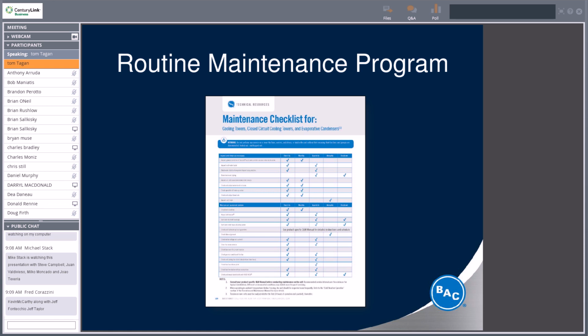So you want to check the general condition of your fan, make sure there's no cracks, make sure there's no loose bolts. You want to check the fan, you want to make sure that if you do have hollow blade fans, that the drain holes are not obstructed. You don't want any water collecting there that can freeze and crack your fan blade. Make sure the fan guard is properly installed.